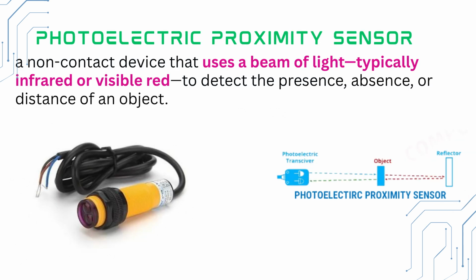A photoelectric proximity sensor, often called a photo eye, is a non-contact device that uses a beam of light, typically infrared or visible red, to detect the presence, absence, or distance of an object, unlike standard inductive proximity sensors that only detect metal. Photoelectric sensors can see almost any material, including plastic, wood, glass, and even liquids.